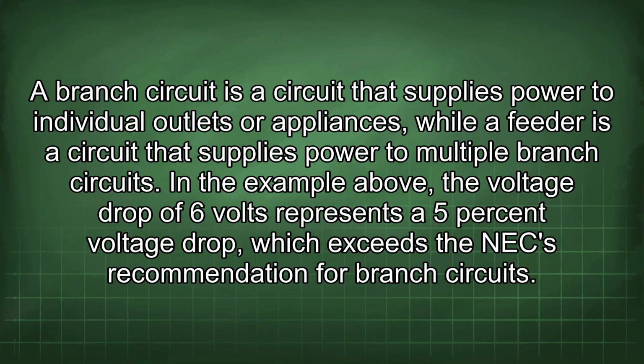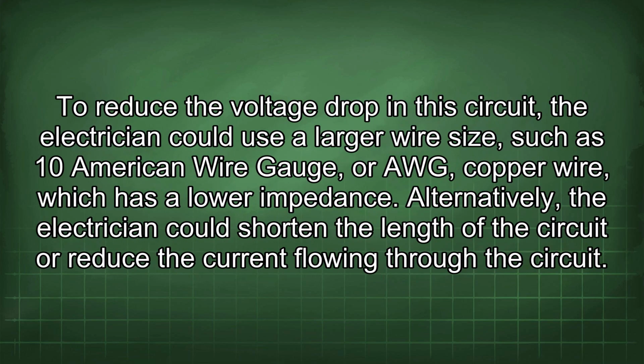In the example above, the voltage drop of 6 volts represents a 5% voltage drop, which exceeds the NEC recommendation for branch circuits. To reduce the voltage drop in this circuit, the electrician could use a larger wire size, such as 10 American wire gauge, or AWG, copper wire, which has a lower impedance. Alternatively, the electrician could shorten the length of the circuit or reduce the current flowing through the circuit.